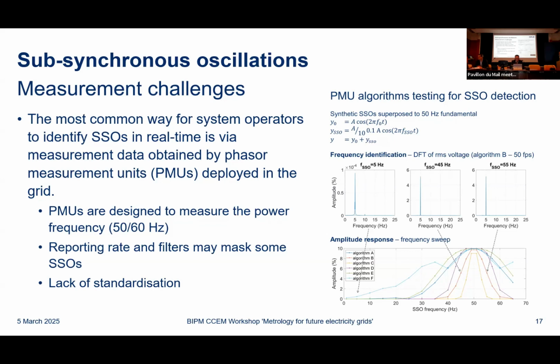And so here on the right-hand side, you can see some work which Stefano, who you've heard from today, has been leading our team on. It shows some initial analysis looking at, for example, a 45 hertz frequency component, which would cause a subsynchronous oscillation. Potentially some of the PMU algorithms might not fully reflect that frequency component. Therefore, these oscillations that are being observed and causing concern may also not yet be fully characterized. So from our perspective, there are some open questions, potentially the reporting rate needs to be considered, and for sure, there's a lack of standardization as to how you implement those types of detectors.